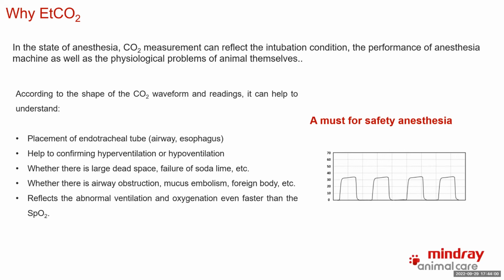And also the CO2 can reflect abnormal ventilation and oxygenation faster than the SpO2, because with the SpO2 technology, it takes a few seconds, a longer time, before it can reflect the changes in ventilation and oxygenation. But for the ETCO2, it's a very short time. You can directly reflect the abnormality. So that's the reason why we need to use the ETCO2 module.